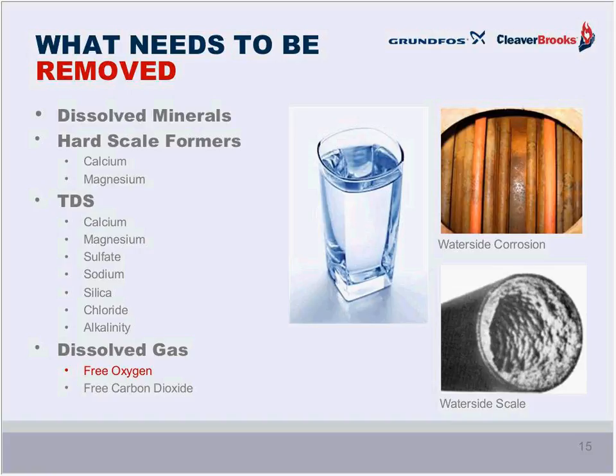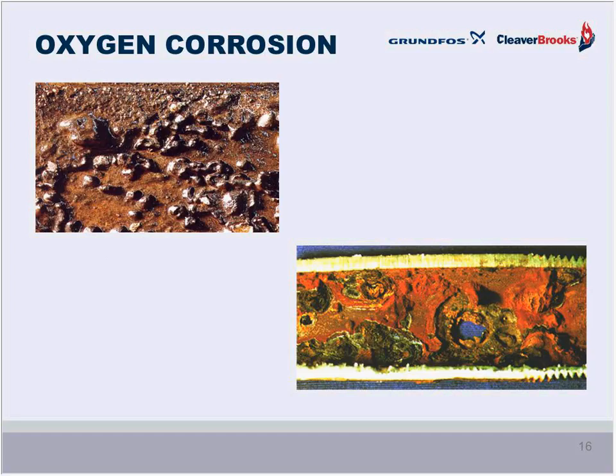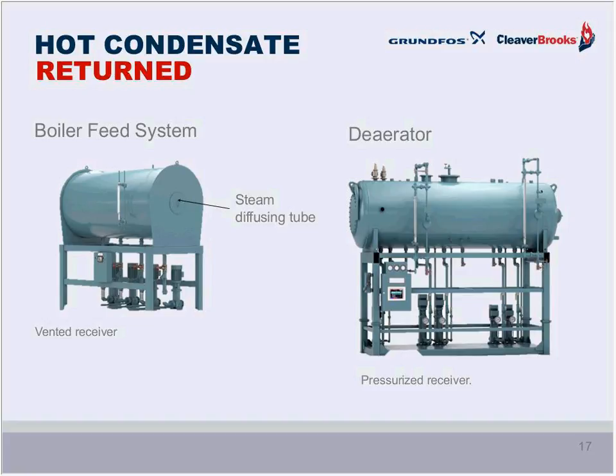And then we have a real nasty culprit which attacks the entire system and not just the boiler. That's oxygen. You can imagine the damage that it does to carbon steel in a very, very short time if left unchecked. And the way at least to start to combat the problem is to employ a means of heating the boiler feed water so as to decrease the oxygen solubility before it can seriously damage the boiler and its connected componentry.